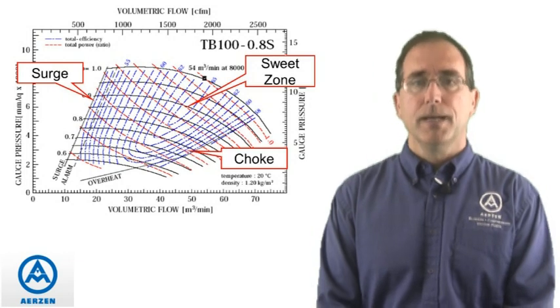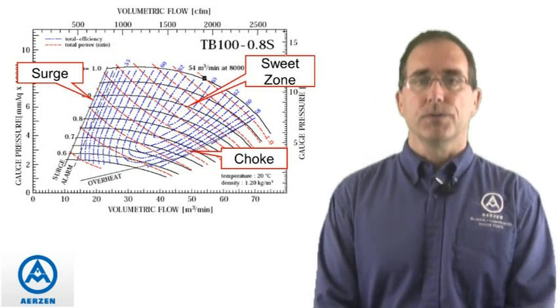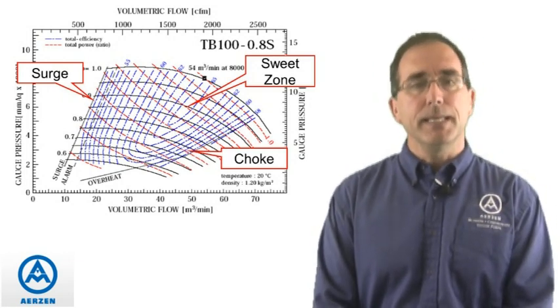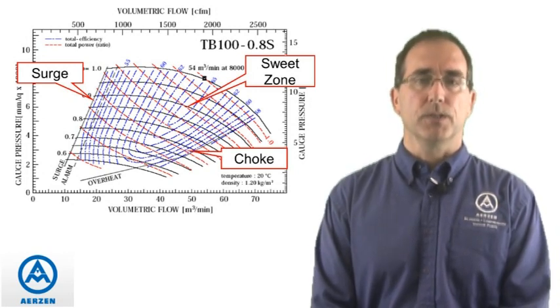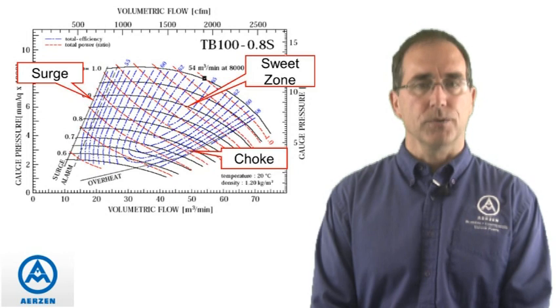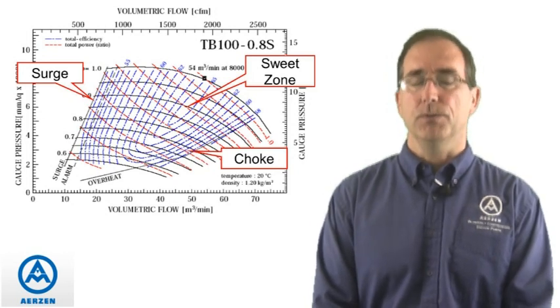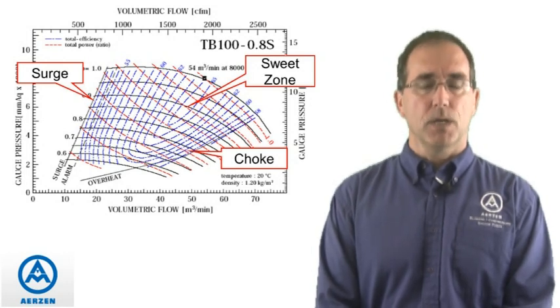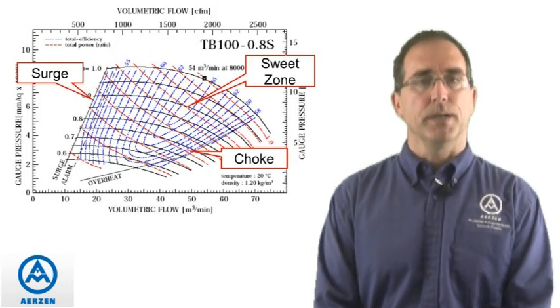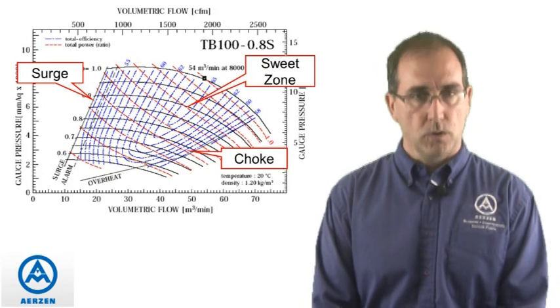Then there's the area of choke and the area of surge. Surge is probably the most critical area of a centrifugal blower, because if you're running on a constant pressure line, which is typical in a wastewater treatment plant, the turndown is affected by the blower running into that surge point, and you want to avoid that at all costs.